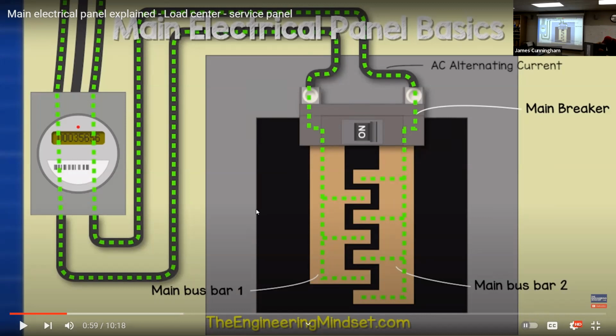So when I turn it off, it's shutting off the power to both tracks here. When I turn it back on, this is a 240 volt breaker, right? Because you've got 120, 120, 240 volt. And on all 240 volt breakers, it's a double switch for each leg of the 120, 120. They have to be joined together. It's NEC, National Electrical Code, that you have to have those two attached.